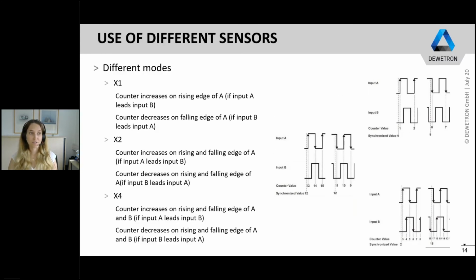Those encoders also have different modes. They are all based on the same principle that if input A leads input B, the counter increases, and if input B leads input A, the counter decreases. Depending on if the rising or the falling edge of input A and B are counted, they count a different amount of pulses. So for example, for the mode X1, the counter increases on the rising edge of A and decreases on the falling edge of input A. For the mode X2, the counter increases on the rising and falling edge of A and decreases also on the rising and falling edge of A.